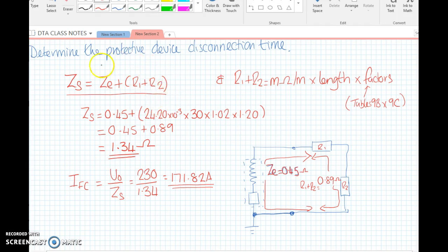There's our impedance: ZS equals ZE plus R1 plus R2. This time we're going to add a bit more accuracy to our R1 R2, because the basic values are for 20 degrees. We're going to put some factors in. To work out R1 R2, it's the milliohms per meter of the cable from table 9a, times the length, which we know is 30 meters, times the factors we need to pick from 9b and 9c.